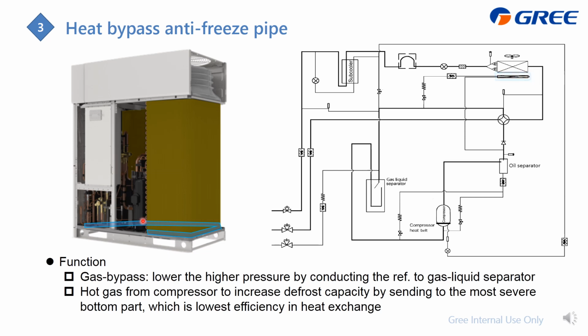On the other hand, during defrosting, the water which comes from the ice will always flow down to the bottom, and when it goes back to heating, the bottom is the coldest, so the water will easily become ice. So just considering this part, we make it another cycle, located here. When we do the defrost, we send the hot gas to melt down the ice on the outdoor heat exchanger, and a partial refrigerant, which is here, will conduct to the bottom to melt down the ice or to prevent the water from becoming ice.